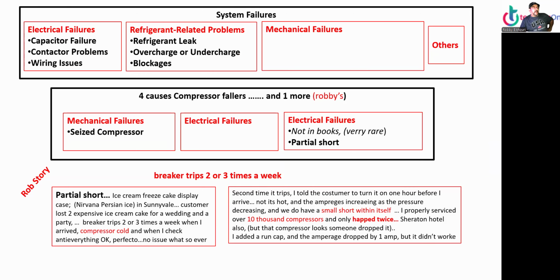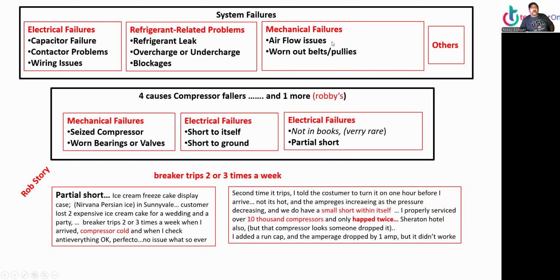We'll get to that later, I guess. Mechanical failures: we have a seized compressor, worn. So mechanical problems are either a broken valve or not pumping. Electrical problems are either short to ground or short to itself. But there is one more, not in books, very rare. It's called a partial short. It happened to me a couple of times. And up there, mechanical, also airflow, worn out belt, and others.